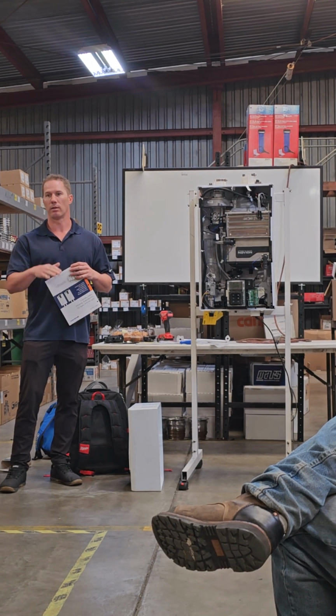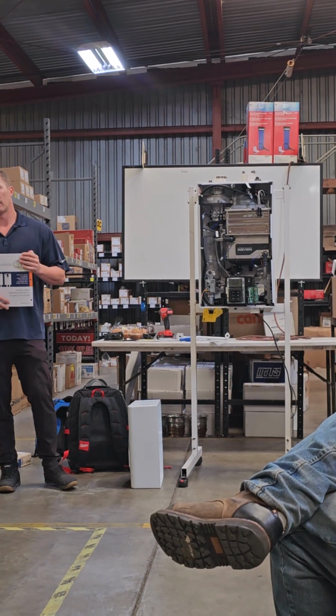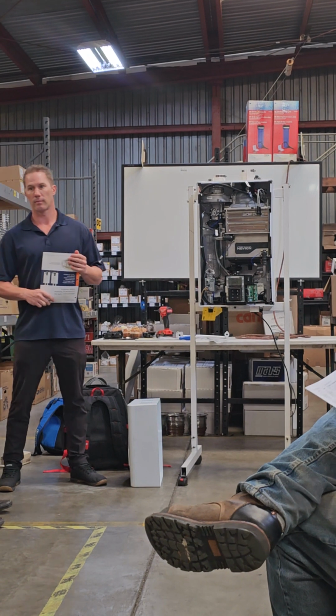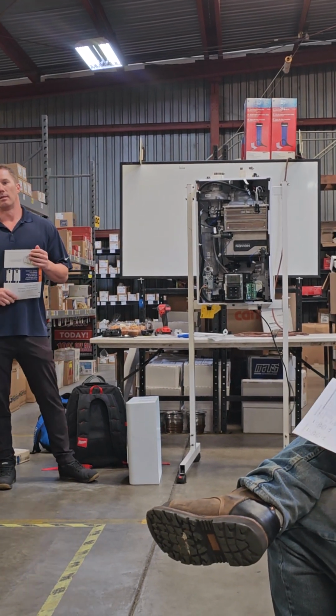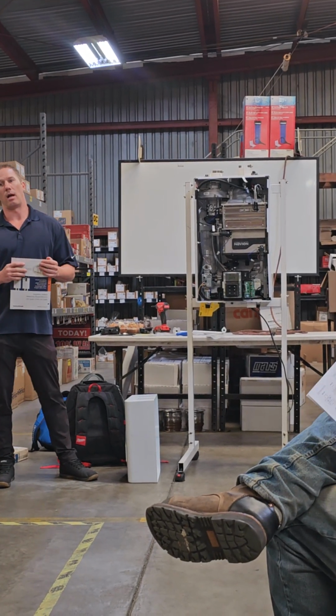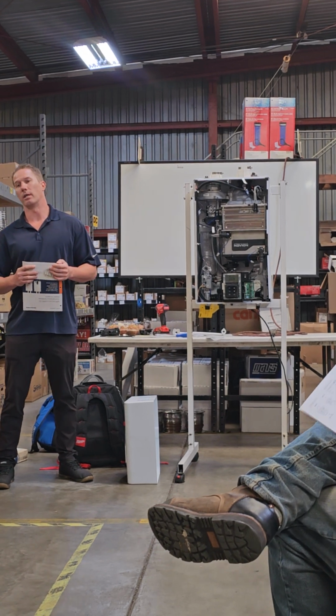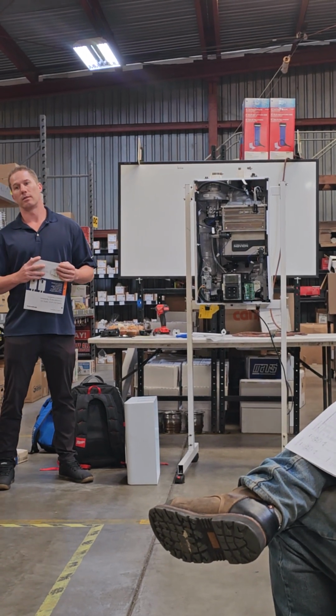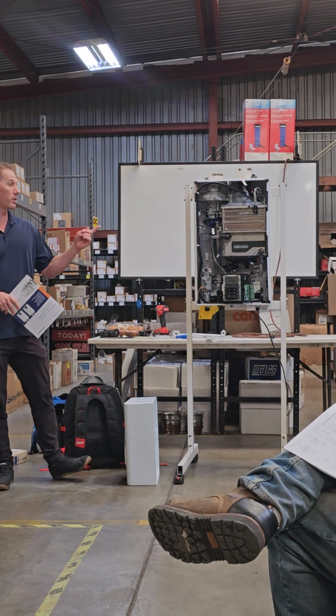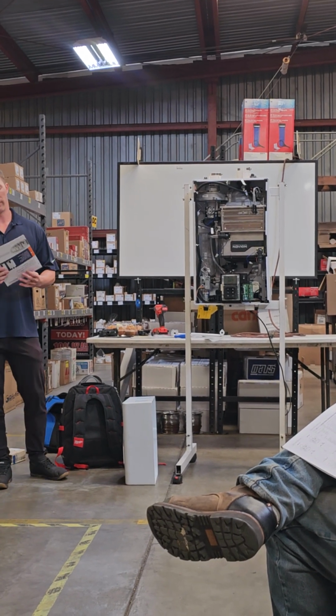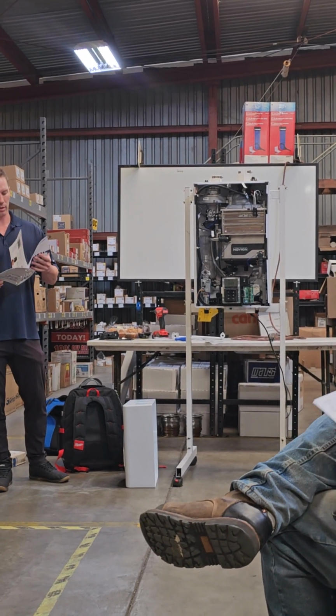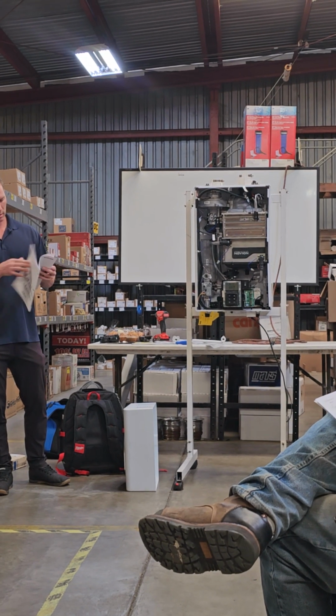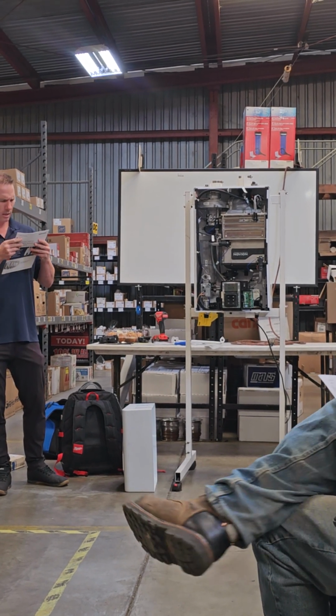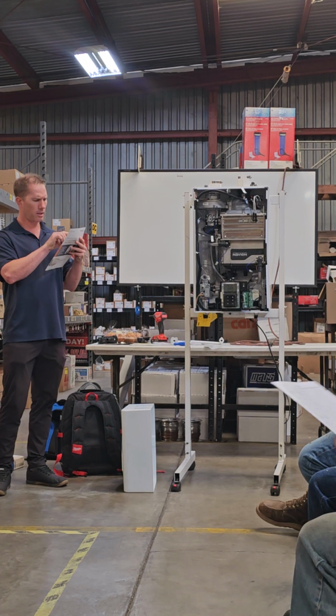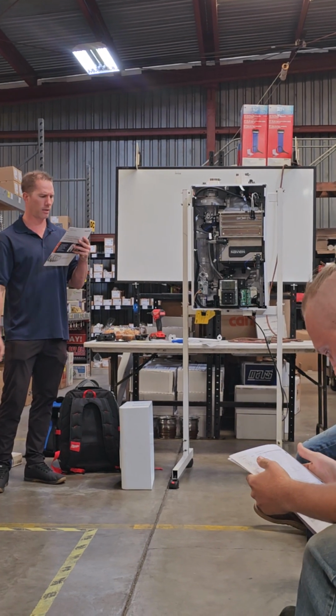It needs to be. So does it say what the burner starts at and what the BTU is? Does it start up like? I have no idea. So the max is probably going to be 199. Yeah, our biggest unit is 199. The smaller units are broken down on here. So there's 150,000, 180, and 199.